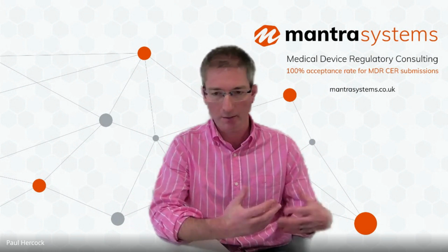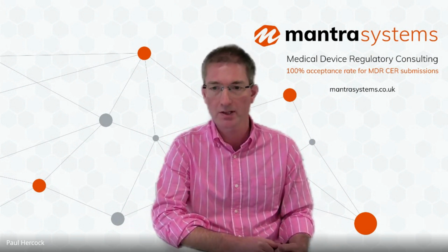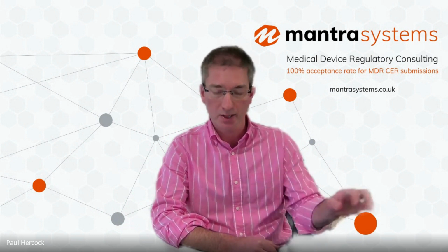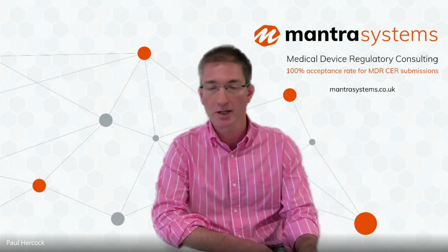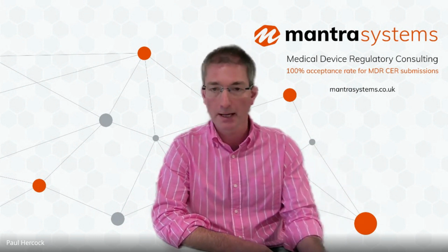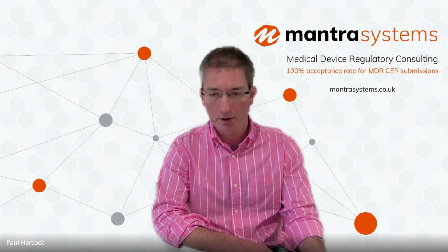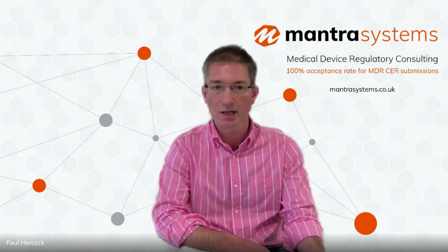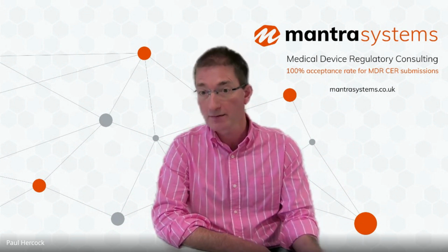And so there's a couple of administrative sections first. Usually a good idea to set out some administrative particulars, the name of the device, the Basic UDI-DI, the risk classification, and the authors of the CER. Then an executive summary, which is like an abstract. It's a summary of the report that follows.